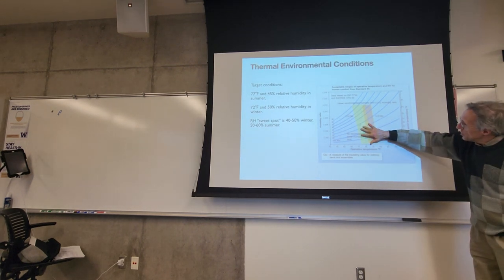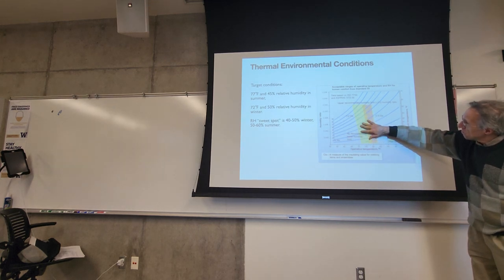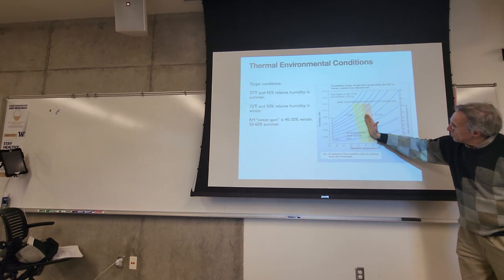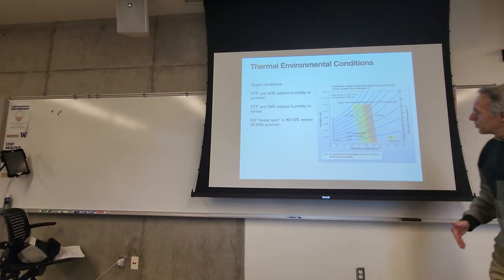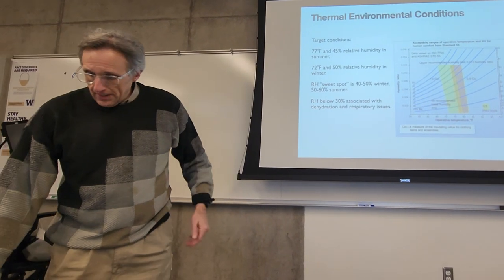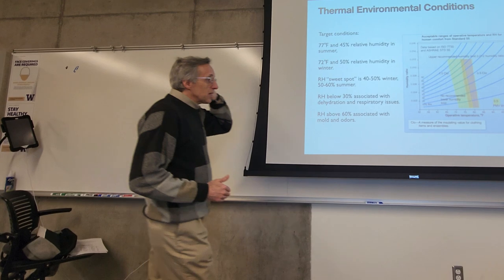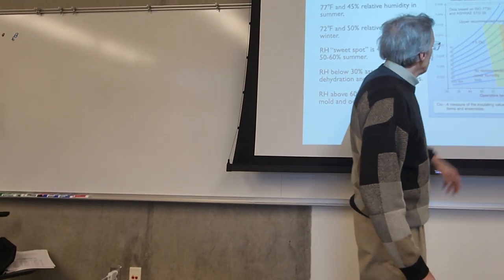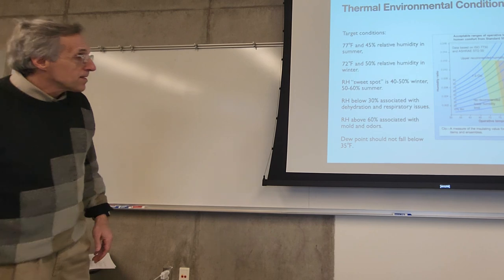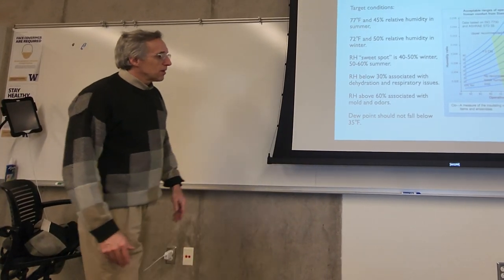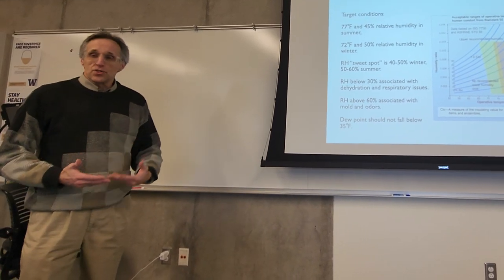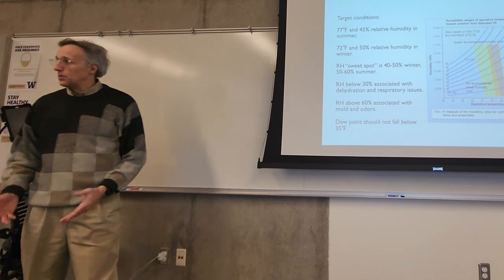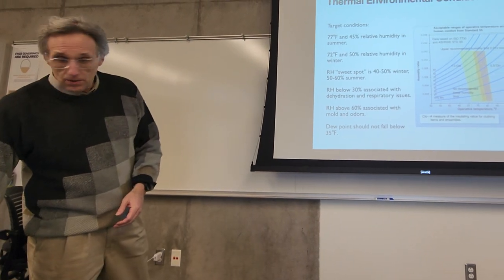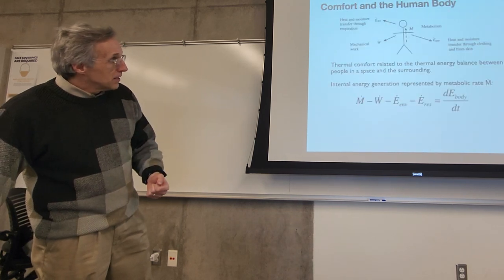And so you can see the range here, and the temperature, as the humidity goes up, the temperature goes down. The temperature corresponds to comfort, and that's what we're supposed to be keeping in mind when we do our design. And then you don't want to go above 60% humidity, generally, because of molds and things like that. Air quality issues become odors. Dew points, keeping dew points above 35 degrees. You get below 35 degrees and you increase the chance of having condensation somewhere in the building. You absolutely do not want condensation in the walls or in the roof inside the building enclosure.